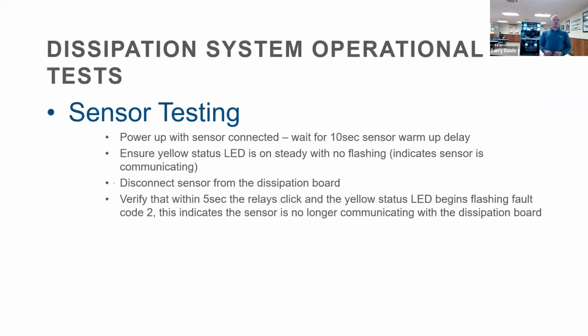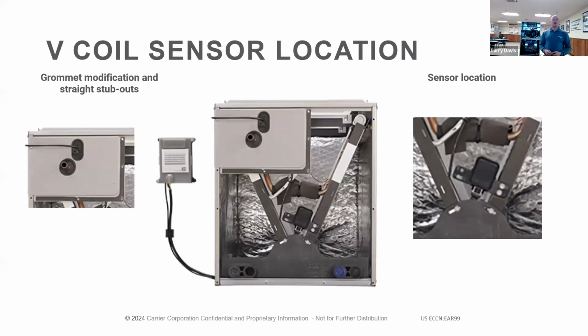Sensor testing. There's a question of, how do we check this, make sure the sensor is working properly? One quick test is to power it up, give it 10 seconds to warm up. When the light comes on and is steady, unplug the sensor. And you should get that fault code 2. And it should go into the dissipation mode. And then we'll see here a little bit later, there's some ways of measuring voltage on the sensor itself.